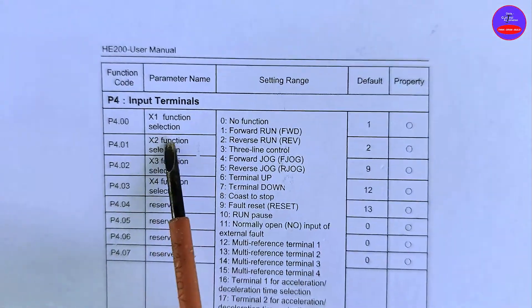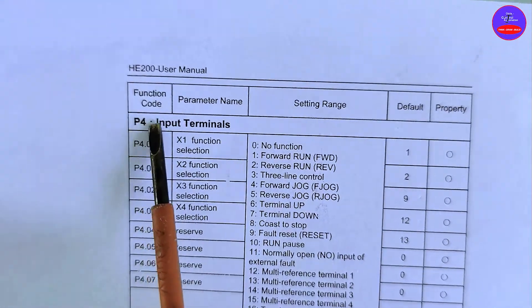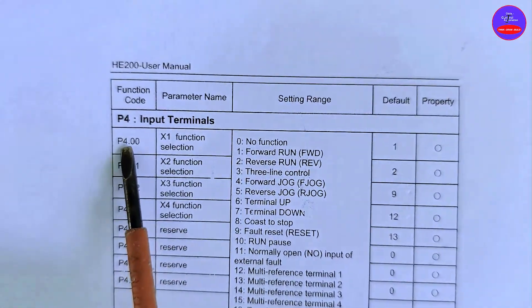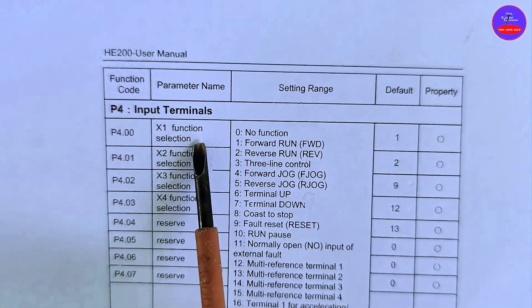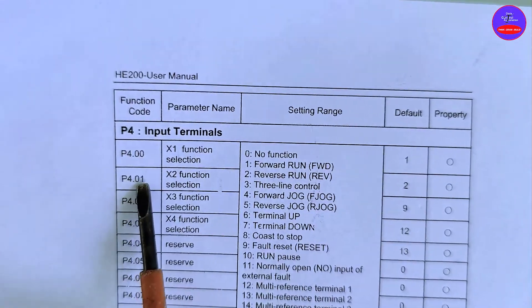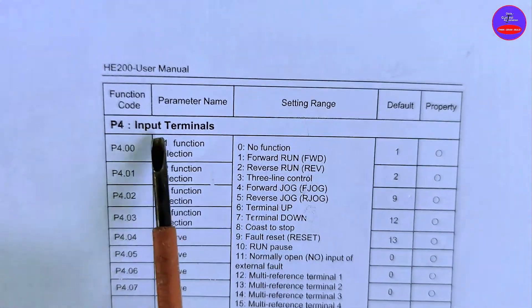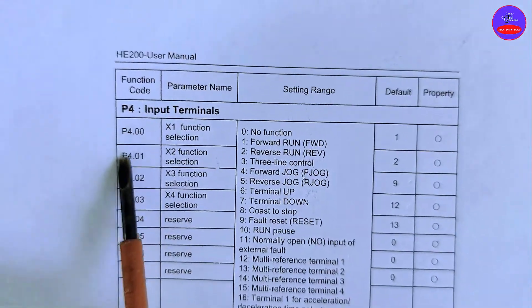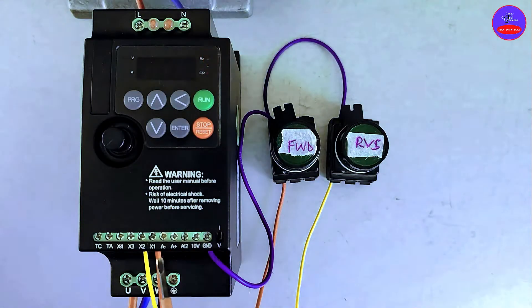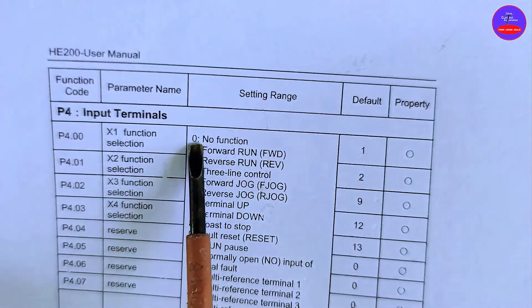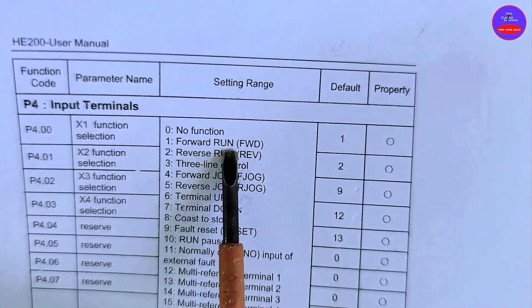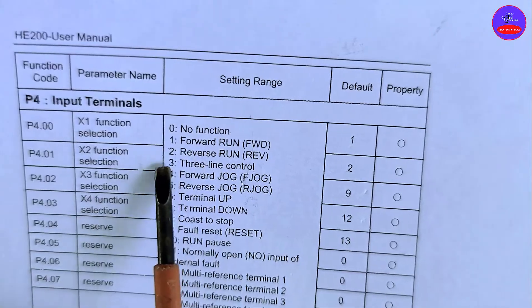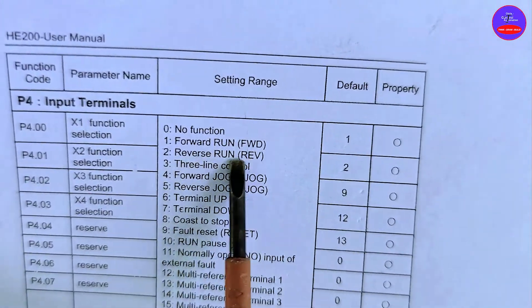On this manual we have P4 input terminals. P4.00 is X1 function selection. P4.01 is X2 function selection. We are going to use these two functions since we selected X1 and X2. Zero is no function, one is forward run, two is reverse run.